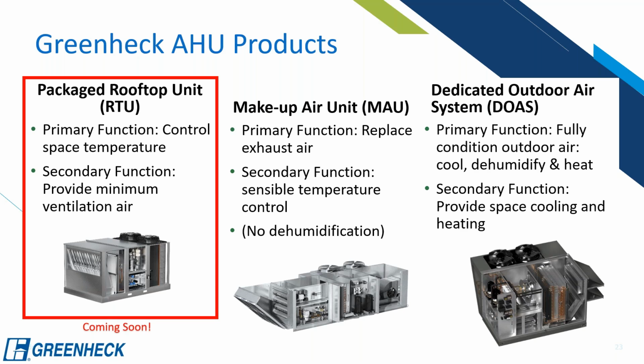So the rooftop unit, the primary function is to control the space temperature. The secondary function is to provide minimum ventilation air. Okay. Makeup air units, the primary function is to replace exhaust air only. It's never to condition the space in a way that, on a psychrometric chart, gets tight control. The secondary function is then obviously to get sensible temperature control, but not really have anything to do with dehumidification. A dedicated outdoor air system, its primary function is to fully condition outside air: cool, dehumidify, and heat. And its secondary function is to provide space cooling and heating.